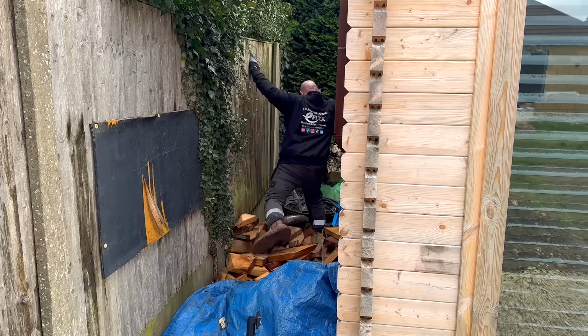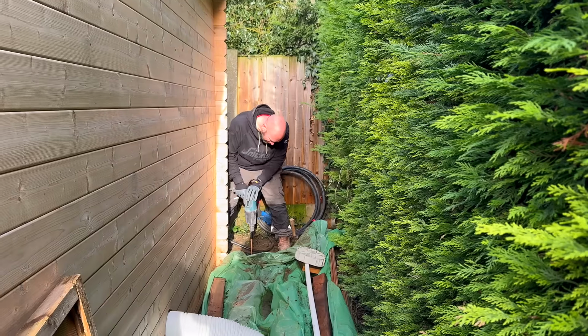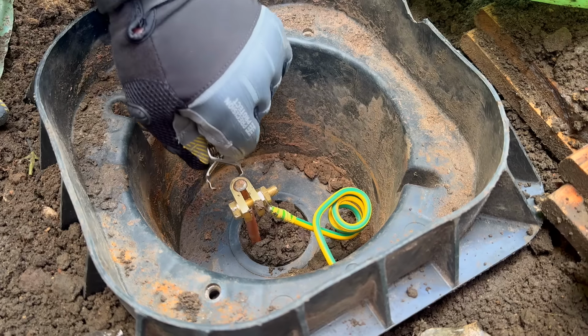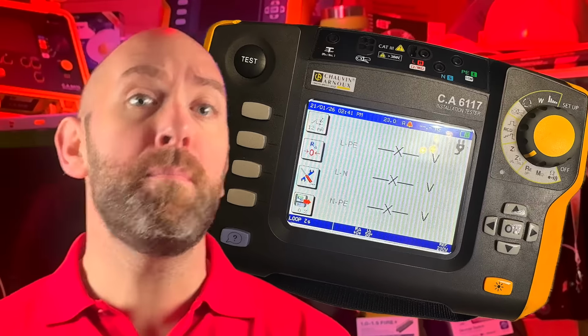When we install an earth electrode, BS7671 does not ask us to guess whether it works, it asks us to verify it by testing. And there are two different tests that we can carry out: earth electrode resistance testing and the earth fault loop impedance test. They are related, but they are not the same thing.